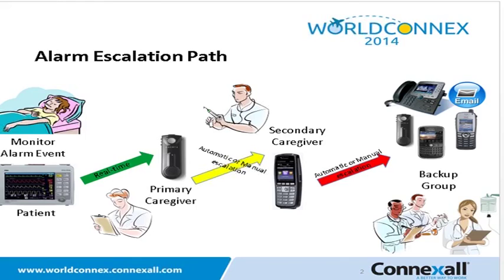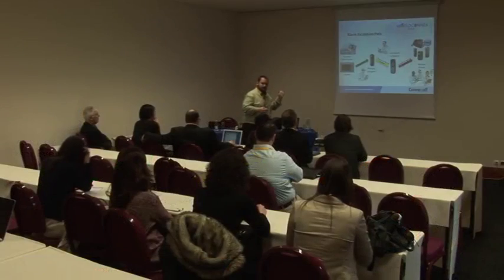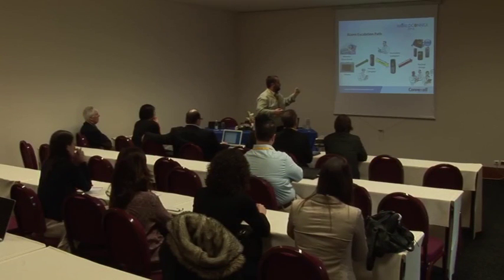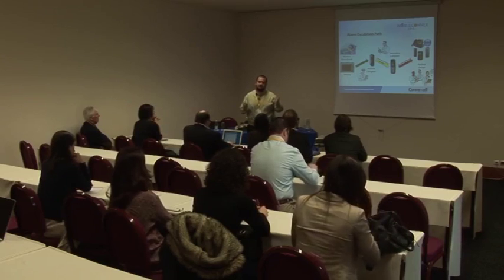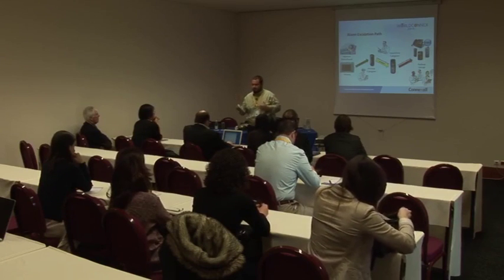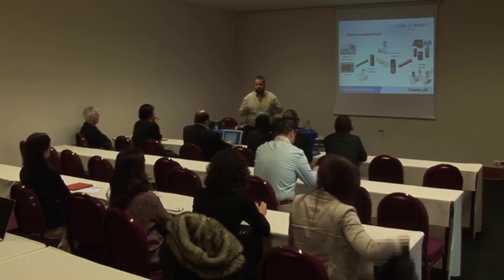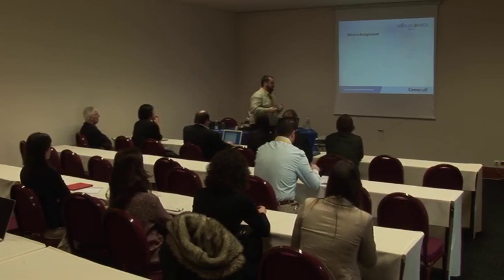If the caregiver knows in advance they will not be able to attend, they can also manually escalate, which could save precious seconds. At the secondary level, the process repeats itself — the user can manually escalate, or after that predetermined amount of time it escalates to what we call the backup level. The timings between levels are independent, so you could have 60 seconds between primary and secondary, and 30 seconds — or five or ten minutes — between secondary and backup.